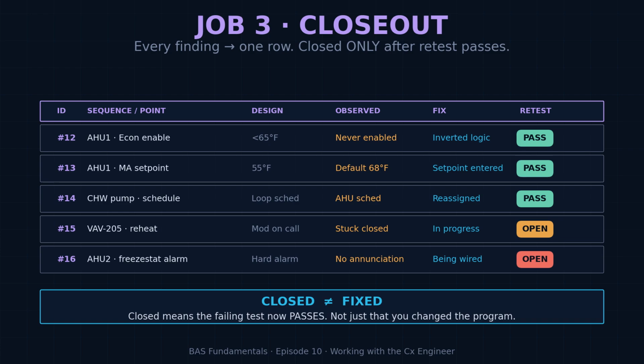A deficiency isn't closed just because you changed the program. It's closed when the test that originally failed now passes. That is a big distinction. Do not let items get closed on your word alone.